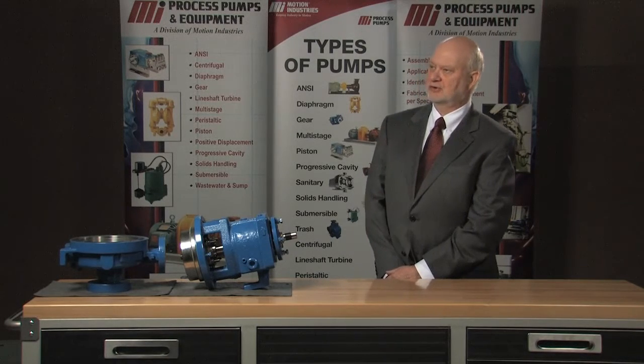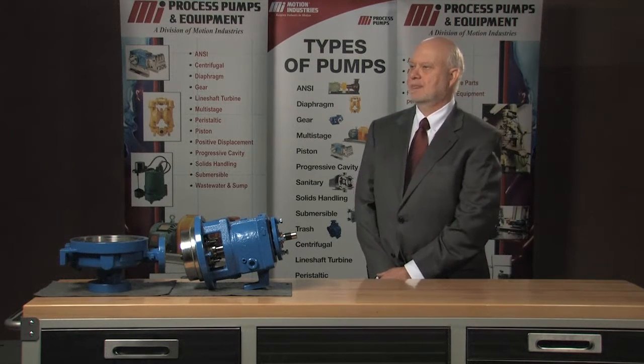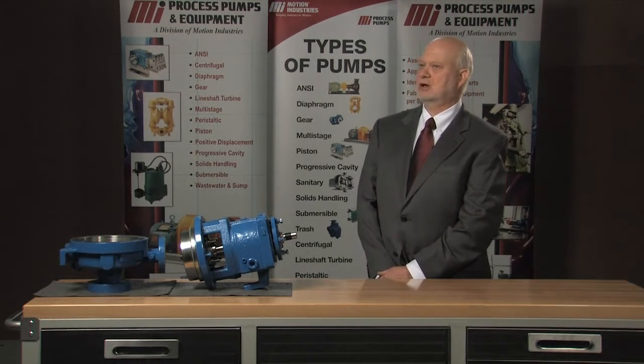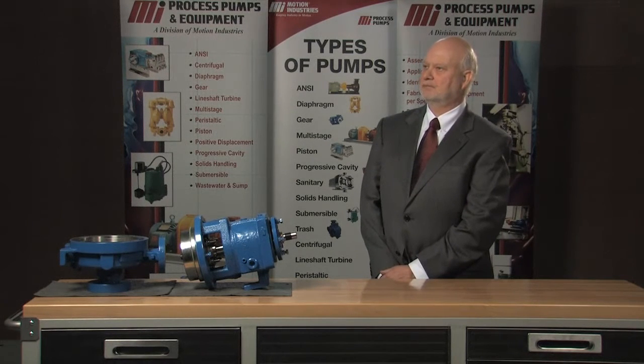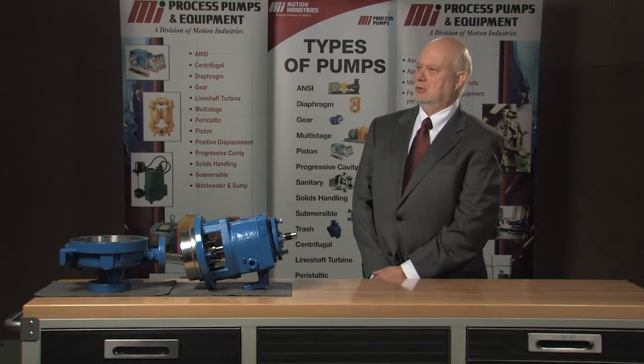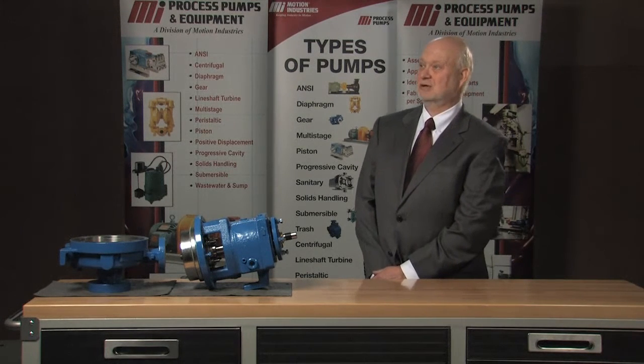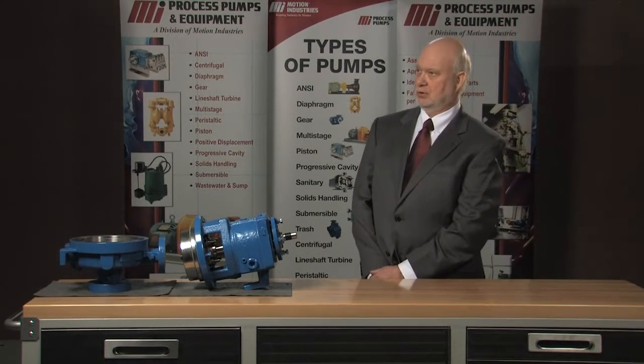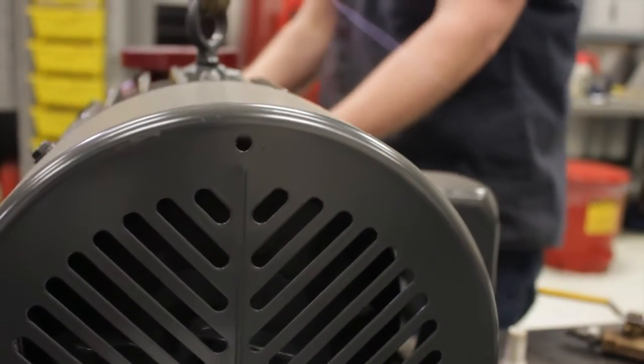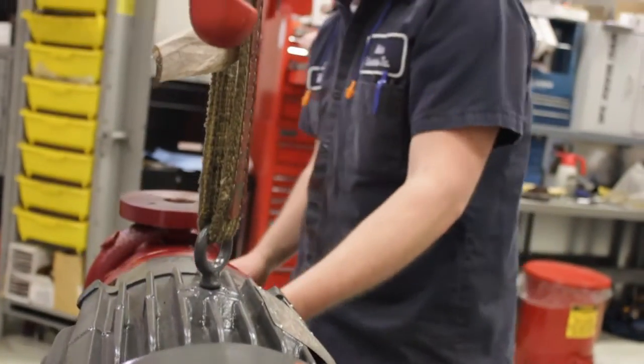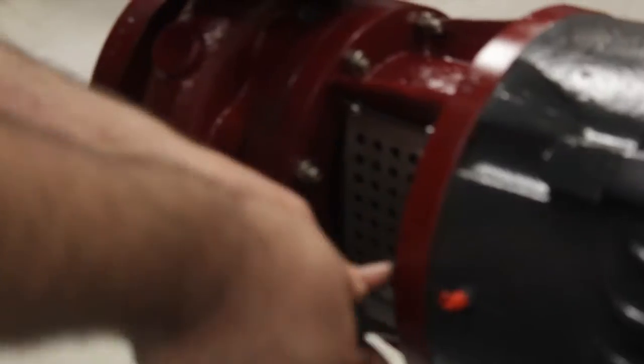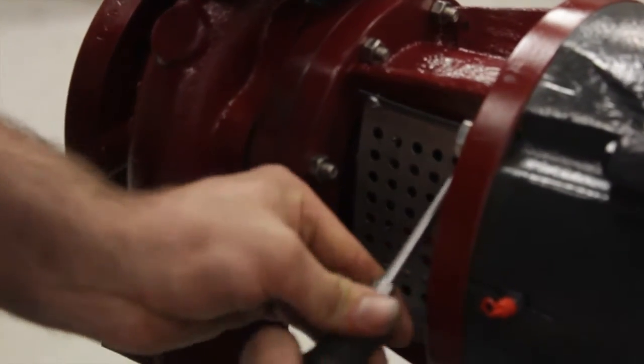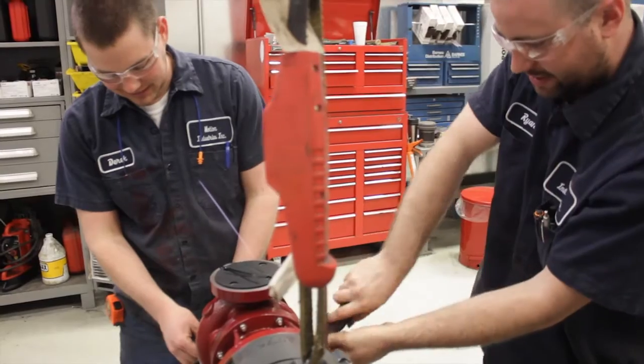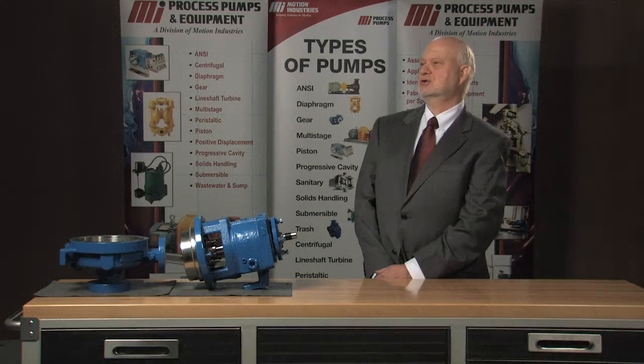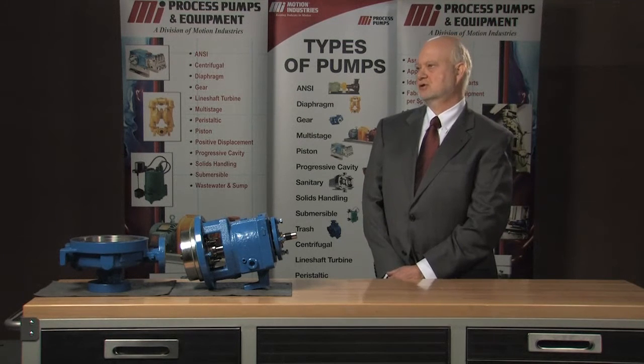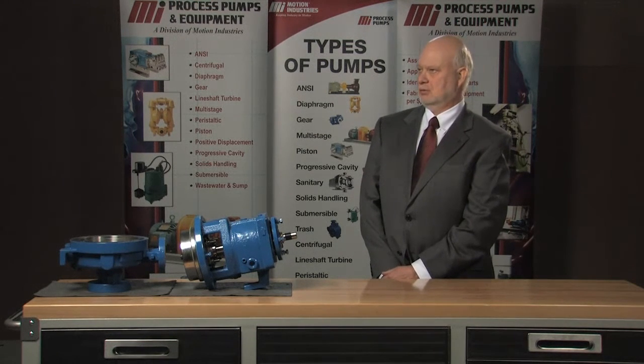Here at Motion, we're able to tear those pumps down, do trouble analysis, and come up with an idea of what went wrong, so we're not just fixing a problem on top of a problem. If there's a root cause solution, we can let the customer know - you know what, you're cavitating this pump, you need to do something with your input, you don't have enough. As a full service provider, we have to be able to repair and rebuild the product we sell. We'll put in new bearings, seals, impellers, rotating assemblies, whatever makes sense. When it gets to be too much compared to the cost of new, then we have to suggest that this is a non-repairable item and they need to do a replacement.